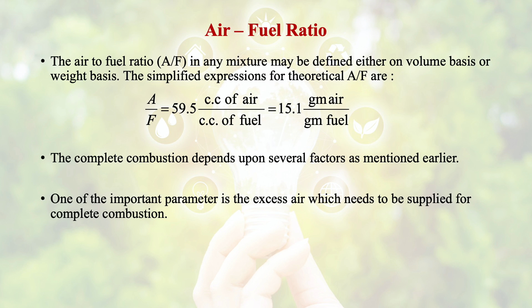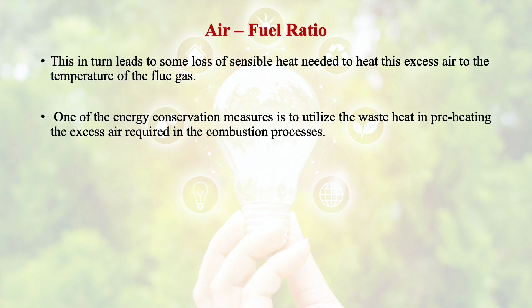The complete combustion depends upon several factors, as mentioned earlier. One of the important parameters is the excess air which needs to be supplied for complete combustion. This in turn leads to some loss of sensible heat needed to heat this excess air to the temperature of the flue gas. One of the energy conservation measures is to utilize the waste heat in preheating the excess air required in the combustion processes.